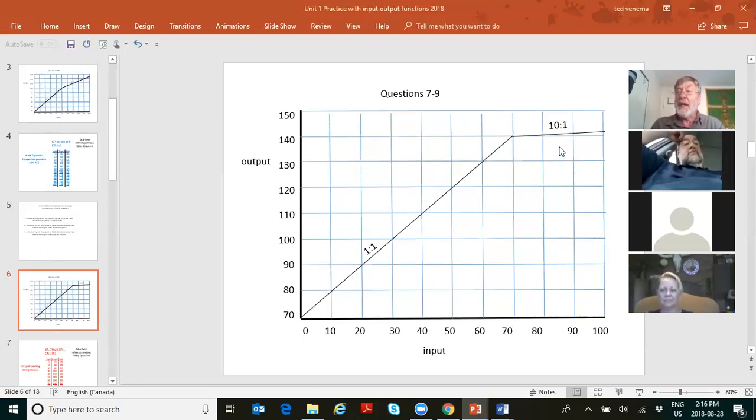So this hearing aid is like the kid in his dad's car, and he sees the stop sign down the road, and he's speeding away, and suddenly, just before the stop sign, he slams on the brakes. This hearing aid is usually high power. It's meant for severe hearing loss, and your main concern is to limit that MPO with a lot of compression, because you don't want to cause more hearing loss. So your big concern here is the ceiling.